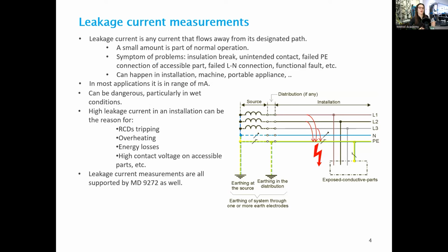Now, let us start with the details about the clamp's abilities and the applications. Now, leakage current is a normal part of operation in more or less any installation or device. Everything leaks slightly. Either the installation is not perfect, or there can be some induction from adjacent wires. These are the types of reasons that there is always some leakage present. The installations or systems need to be designed with this leakage in mind. We're talking about sizing of the wires or RCD selection, and there are other similar considerations that must be taken into account.